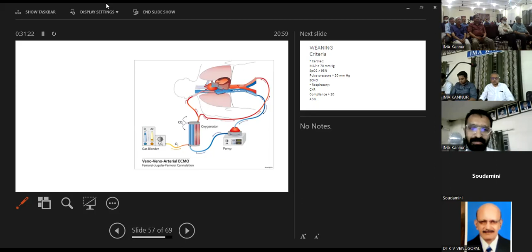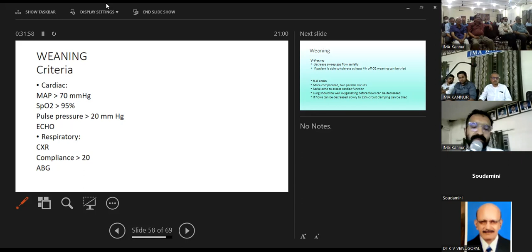So, the weaning criteria. Weaning starts once there's improvement in the condition of the patient. For cardiac status, if the mean arterial pressure is over 70 with an SpO2 of over 95 and a pulse pressure more than 20, and echo shows an improvement in the EF, we start weaning from VA. For respiratory VV ECMO, we check the chest X-ray daily, we check the ABG and the compliance of the lung. If it is more than 20, we plan weaning. Weaning from a VV ECMO is by decreasing the FiO2 and the sweep gas flow. We decrease it to minimum and gradually increase the ventilator settings. And then we give a trial off.